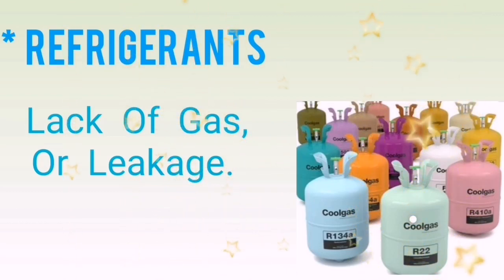Step 5. Refrigerant. If the outdoor fan and compressor are working and you are not getting cool air inside, it means there is a lack of refrigerant. Easily you can check: the discharge pipe should be hot and the suction pipe should be cooler. If you see the discharge pipe is cooler than the suction, it means there is a lack of refrigerant. Or you can easily check by the pressure gauge according to the pressure of the refrigerant. Try to find the leakage and braze it, then do the vacuum and charge the refrigerant.